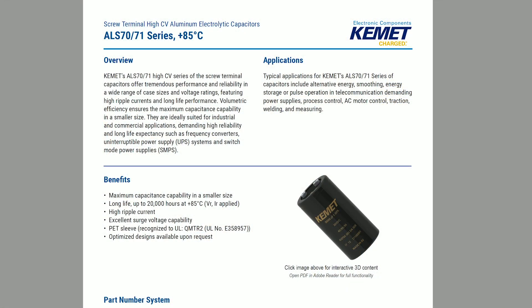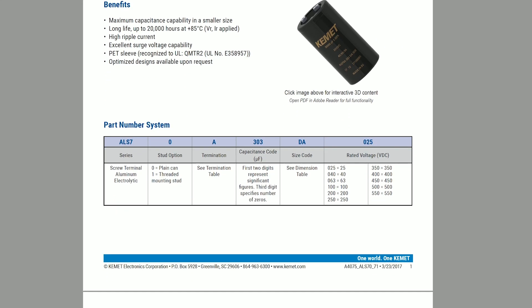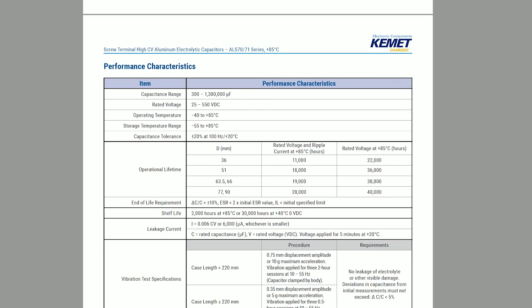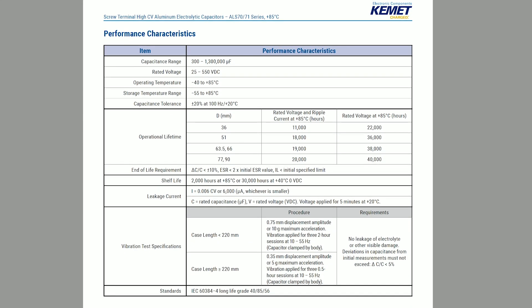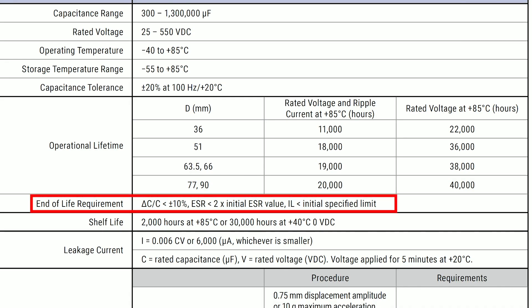Parametric failure comparisons should be made between manufacturers using the same criteria. Kemet's parametric failure criteria can be found in our series data sheet. For example, our ALS70 aluminum electrolytic high CV capacitor — we can take a look at the data sheet and see end-of-life on page two. The wording is a little confusing, but it shows that if one of the following conditions is no longer true, the capacitor is considered end-of-life.